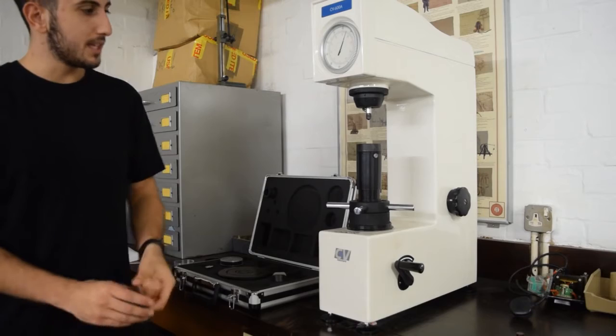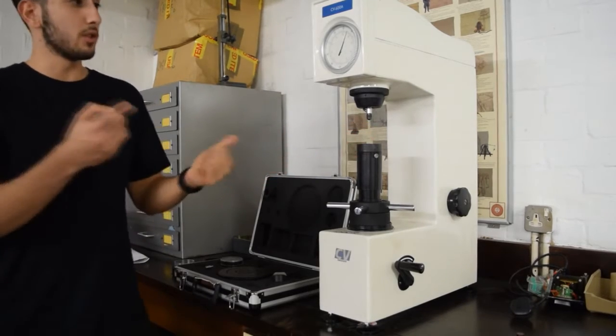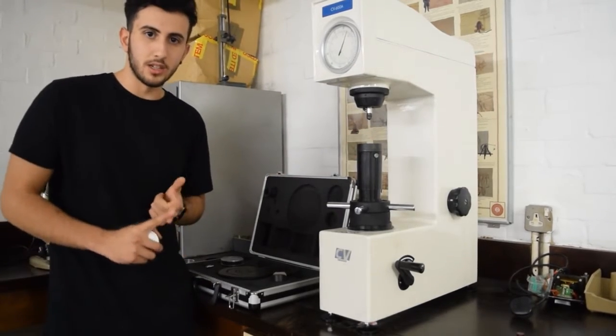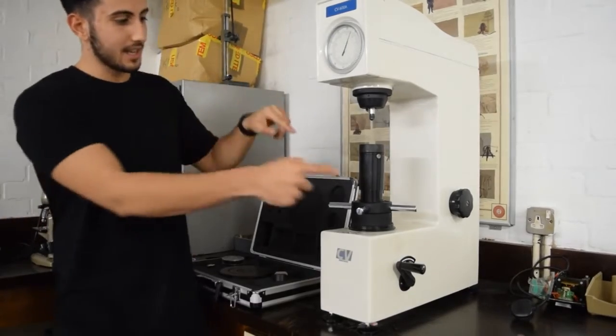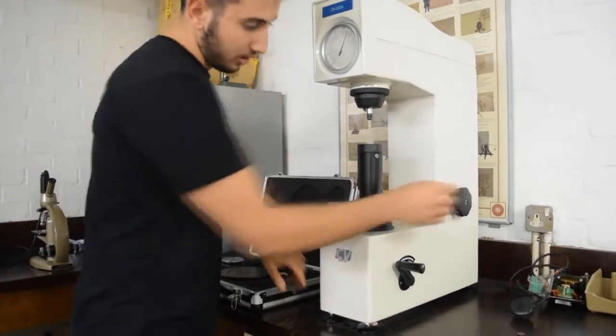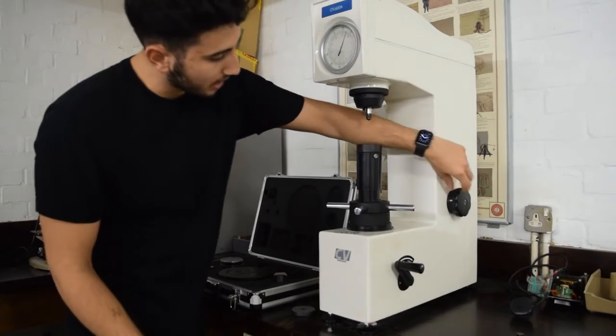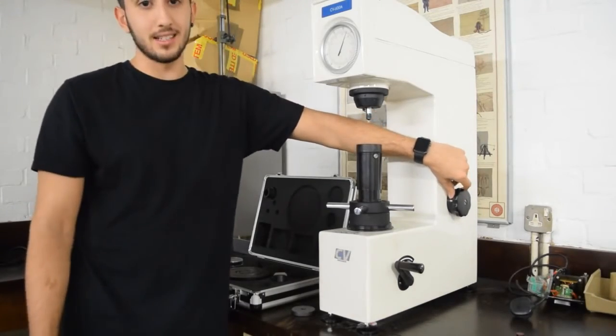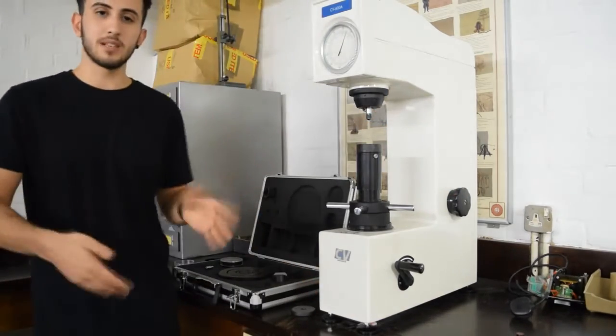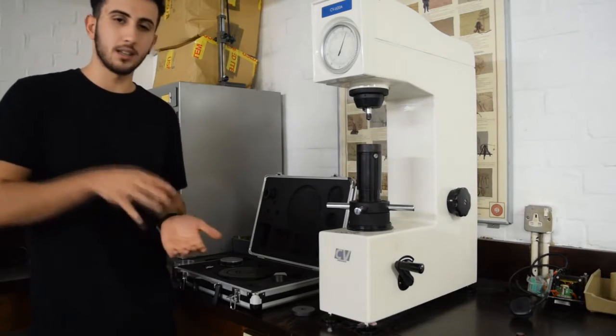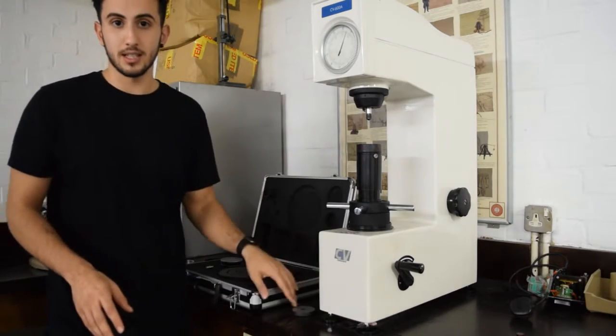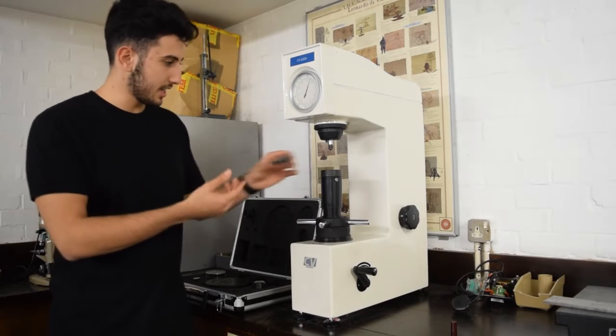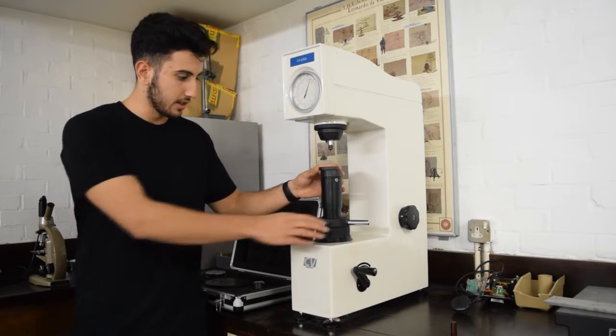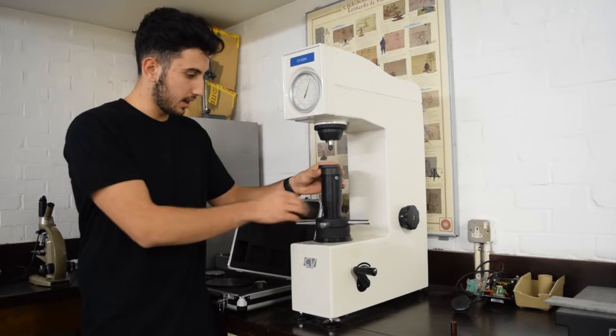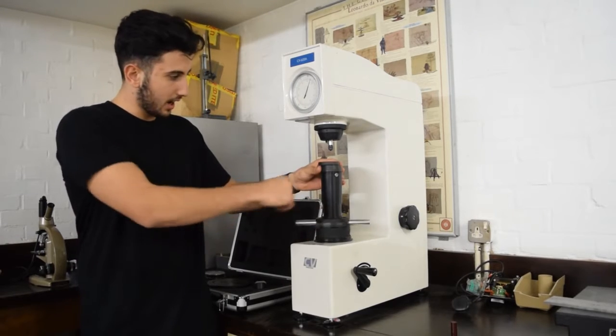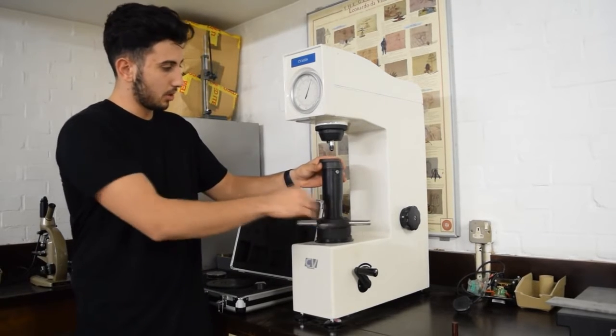So with a B scale indenter, first of all you have to apply a minor load and then a major load. The major load has preset settings on the side of this machine, and we just make sure that it is reading 980. You have a specification sheet that shows you the loading, the minor and major loadings of different scales. Next we'll put our test specimen onto the bench and use the feed handle to bring it all the way up to the ball indenter.